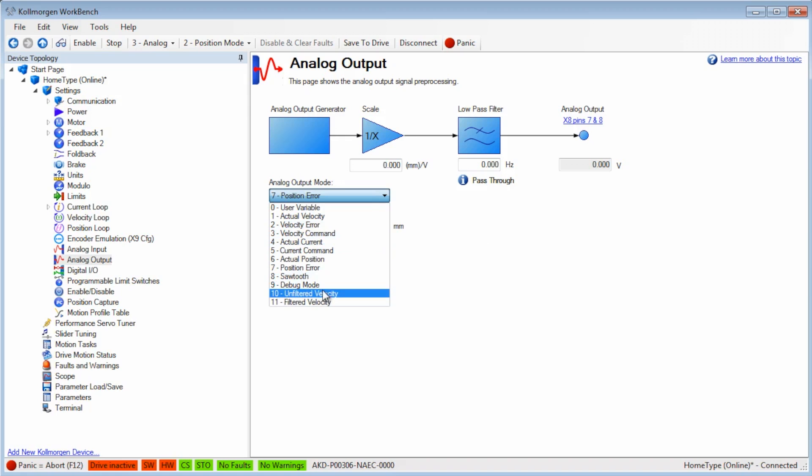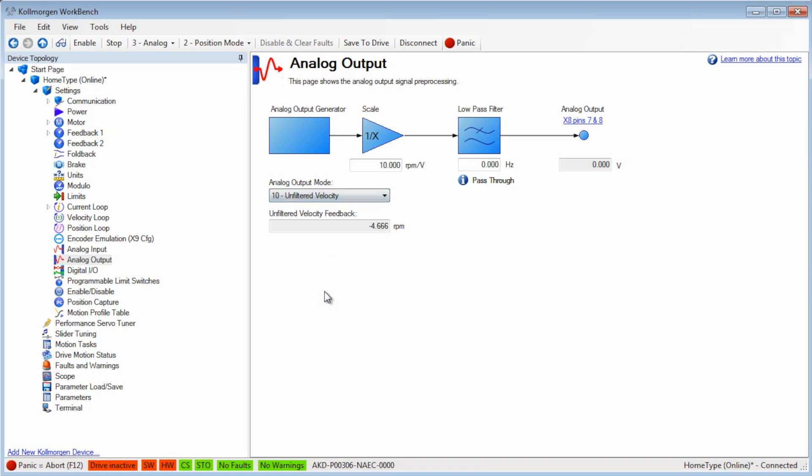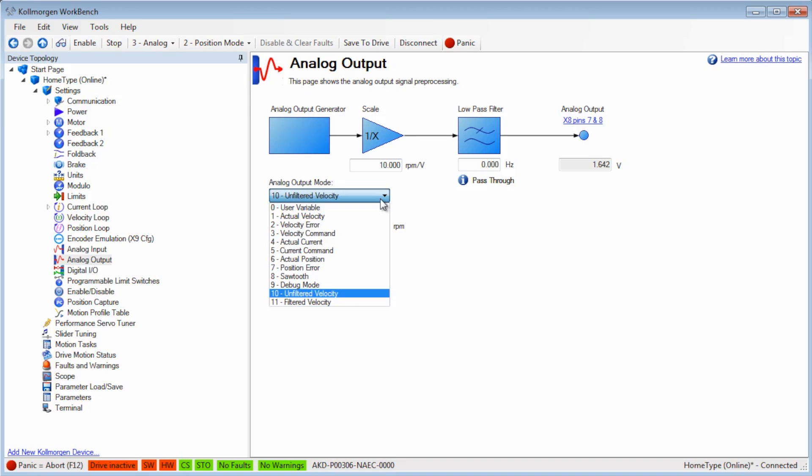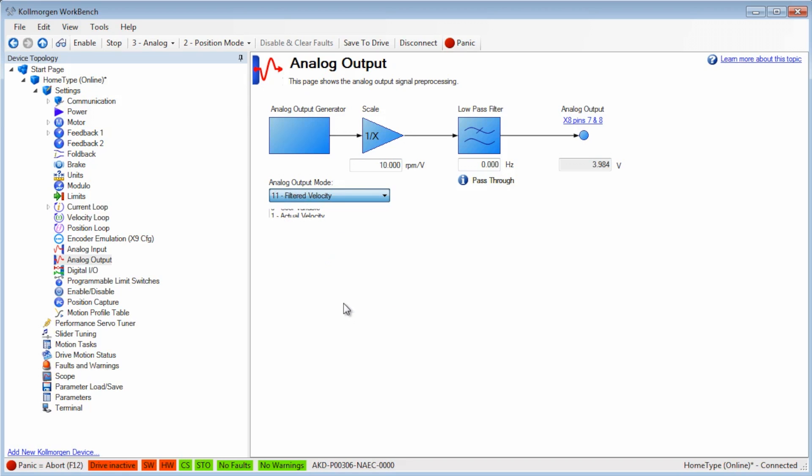Mode 10 is unfiltered velocity or raw velocity feedback before any filters are applied. Mode 11 is filtered velocity using a 10 Hz low-pass filter and is the same as VL.FB or velocity feedback.